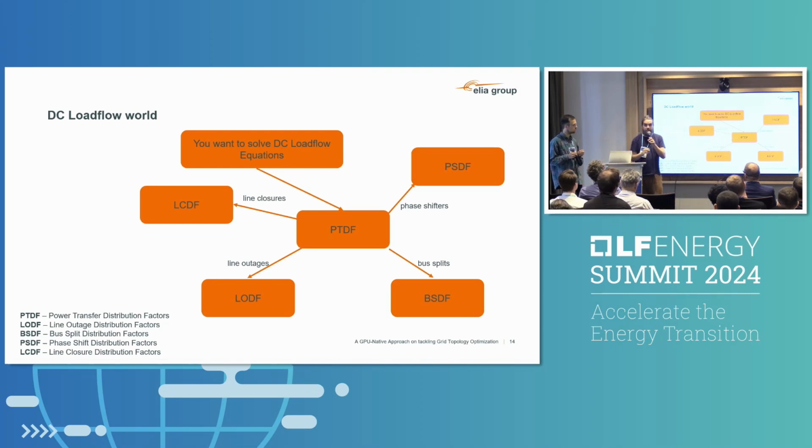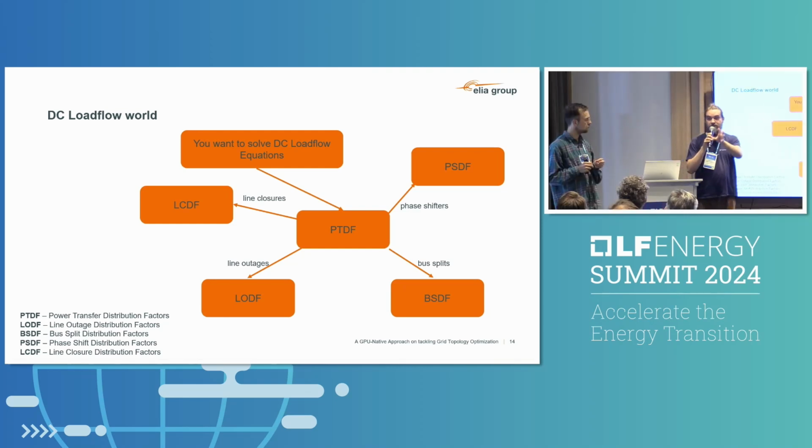We probably have like 50% more impact, or maybe even more if we look at phase shifters. We might have 50% impact or even more if we optimize on a larger grid and not just one. So for example, what we see right now, if we have time steps in Germany where there's a lot of congestion in the D2 area, in the TenneT area, we can solve that congestion in the 50 Hertz area. So we can actually pull problems to the 50 Hertz grid, but the overall number of problems goes down. So there's a very high coupling between the grids.